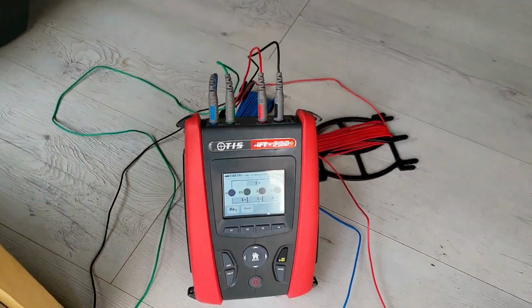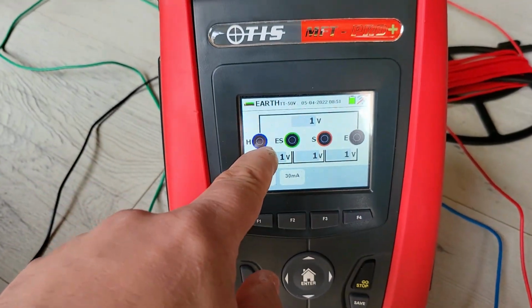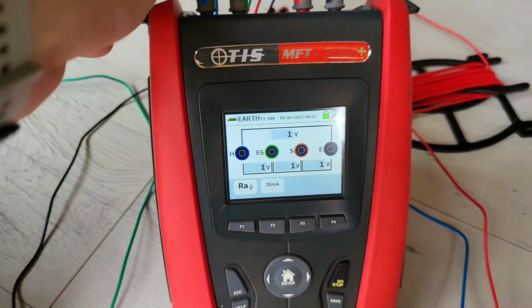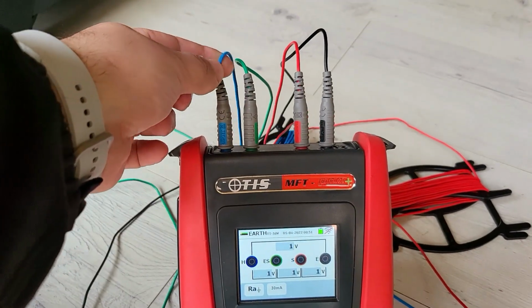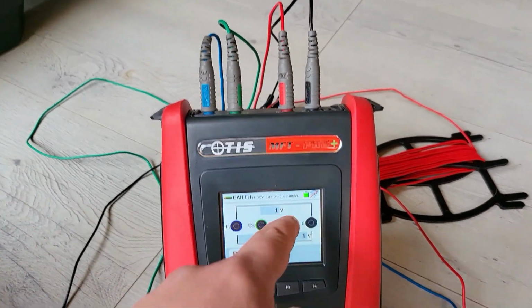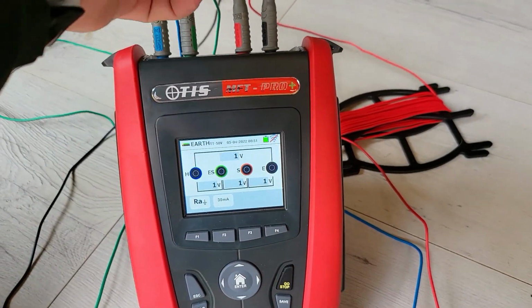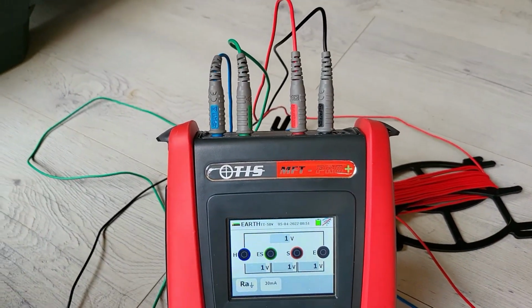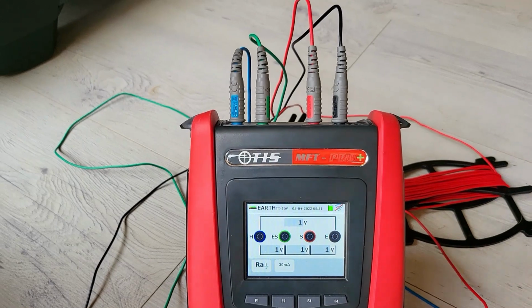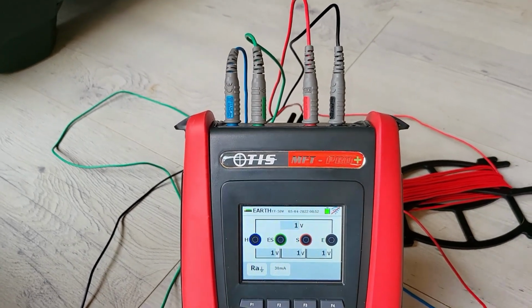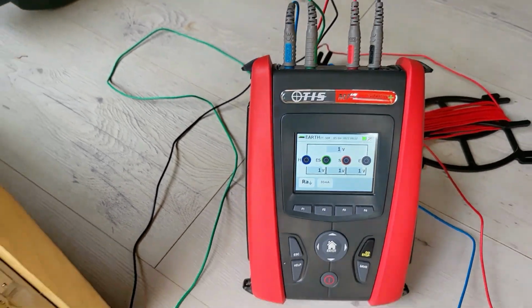Just to say from the beginning, this H probe is your current probe, if you like - this blue wire here goes off to the furthest point. Then your voltage probe is this S1, which you want at the midpoint between the final current probe and the earth electrode under test itself. But we'll have a look at all of that.